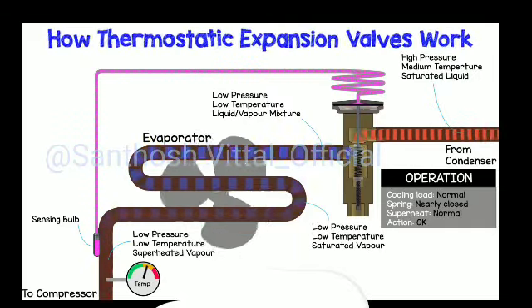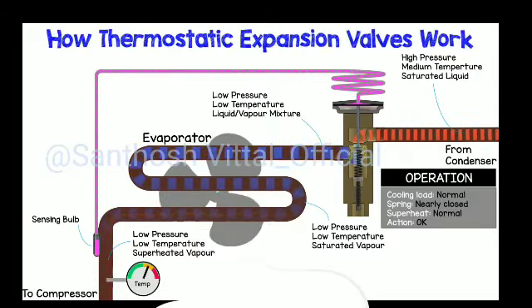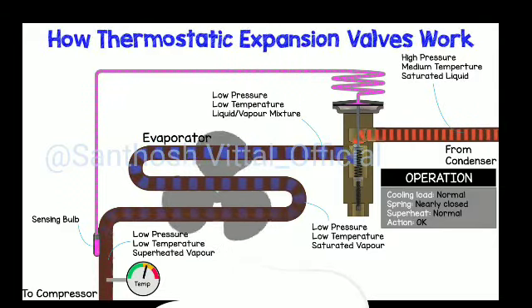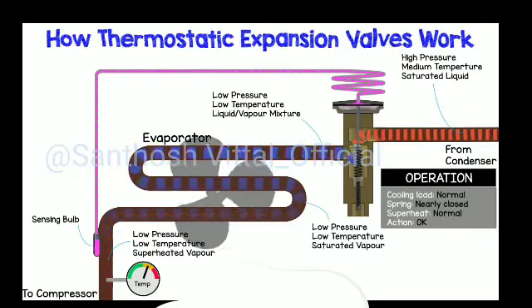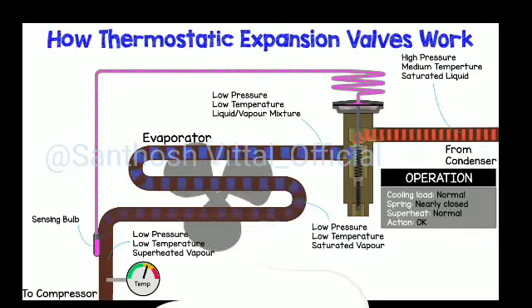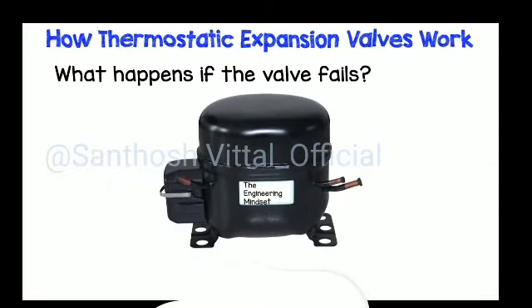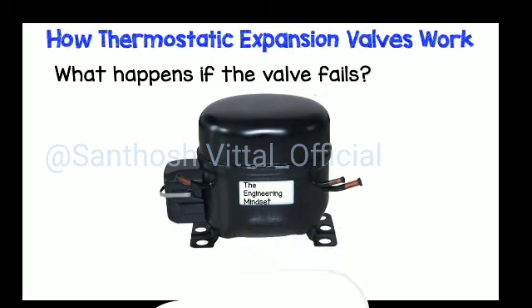Now, all of this happens automatically using this type of valve, which is why it is so popular. There are other electronic versions of this valve which can provide even more precise control, but we'll look at that in a later video. So what happens if the valve fails or the wrong superheat settings are used? Well, if the valve didn't react to the superheat, it could let liquid refrigerant pass straight through and into the compressor. Compressors hate this because liquids can't easily be compressed, and so the compressor will, well, maybe not to that extreme, but the liquid will damage it, so make sure the superheat setting is correct.